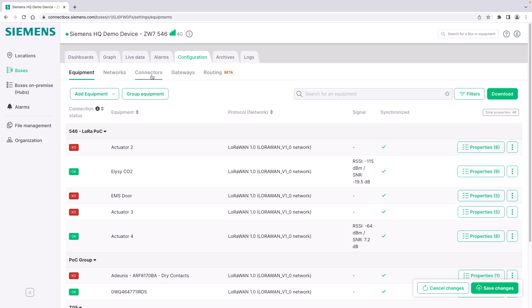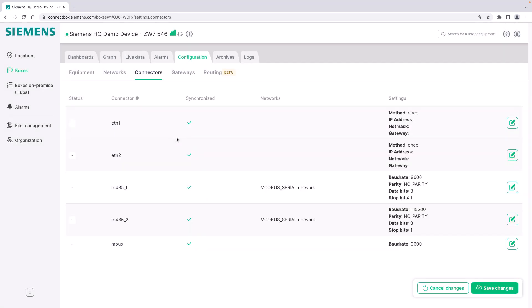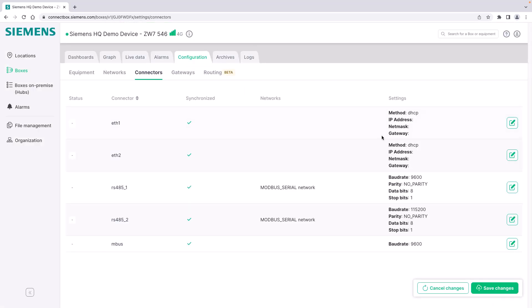The very first step when you have a new box is to go to the connector tab. You review the different physical interfaces that are available and you set the parameter of each of those interfaces. For example, the IP communication method for the Ethernet ports - you can choose DHCP or a manual IP address - and you can also set for example the network parameters for the serial networks, for example to use Modbus protocols. The device also has a dedicated M-Bus interface.